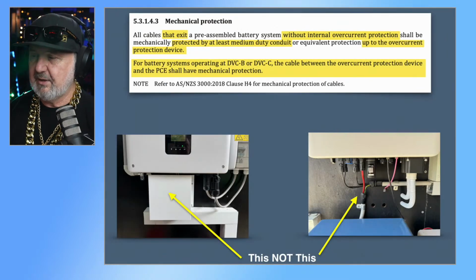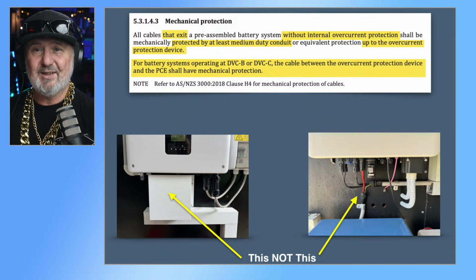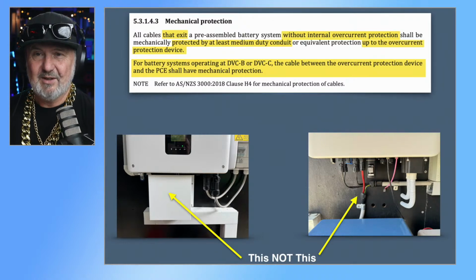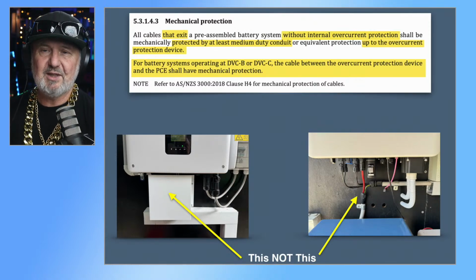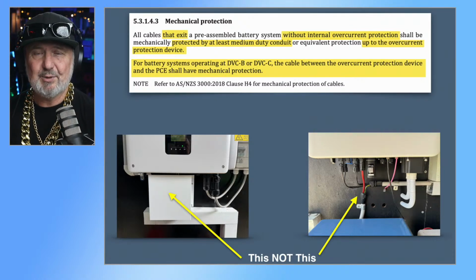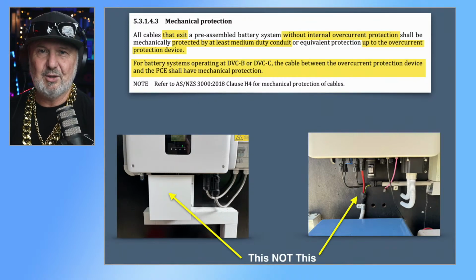Okay, and now we're getting on to mechanical protection. Now this is yet another one that I was tripped up on. Kind of so used to just plugging PV into the bottom of an inverter. We know that 4777 part 1 says you can have 300 mils of mechanically unprotected cable at the PCE, as long as it's in a location unlikely to be damaged. And therefore, sort of the interpretation is that underneath the inverter is a kind of protected zone, and so flexible cable is commonly used to connect PV arrays into the inverter.